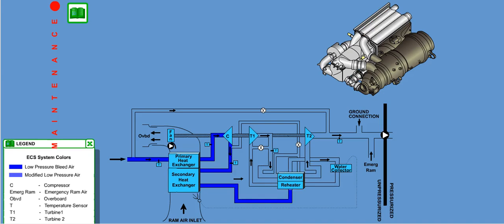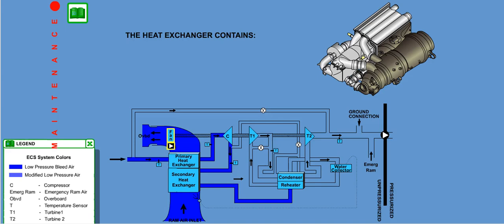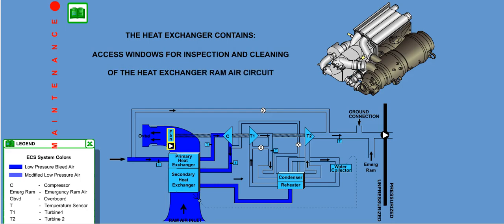Both bleed circuits are cooled by ram air in series: first the secondary, then through the primary heat exchanger sections. Ram air exiting the heat exchangers enters the fan inlet diffuser housing and is either pulled through to ambient by the fan or passes through the fan bypass check valve. The heat exchanger contains access windows for inspection and cleaning of the heat exchanger ram air circuit.